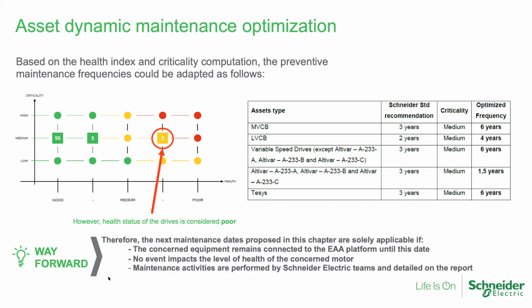For example, from an actual customer, we can shift a medium voltage circuit breaker's maintenance cycle from 3 years to 6 years, or a low voltage breaker from 2 years to 4 years. However, some drives present health issues—over-braking, over-temperature—so for those particular drives we want to shorten the maintenance cycle to make sure they don't fail on the job.